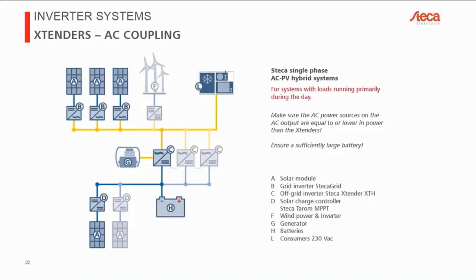So what you can do is the Xtender can simply switch the frequency. We'll go, let's say, from 50 to 54 hertz or 52 hertz. You can set it however you like. And this will make absolutely no difference to your loads. They will continue to run normally. But your PV generator or your wind generator will notice that the frequency of what it thinks is the grid has switched to a higher level and that it needs to stop producing. So that's how you prevent your battery from being overcharged.